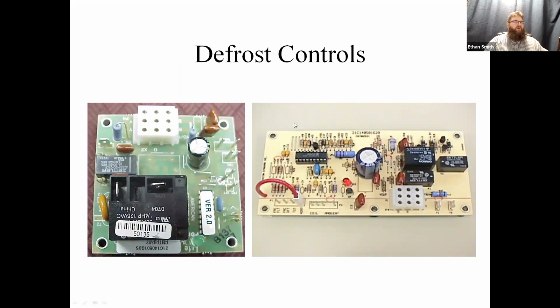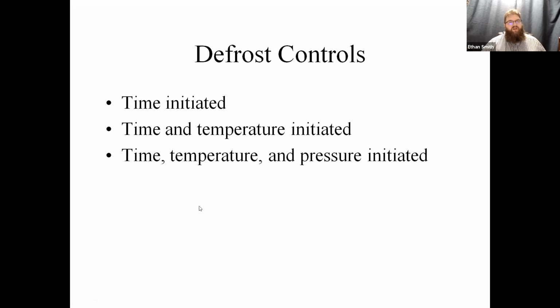Okay, let's talk about defrost controls here, guys. So there's several different types of defrost controls out there. The old ones were just time initiated. You'll still see these on refrigeration systems for like walk-in boxes, things like that, where it's just simply a timer. It defrosts for X number of minutes every hour or every 2 hours. Okay. We also have time and temperature initiated, where it'll actually take a temperature of your evaporator and determine whether it needs to defrost or whether it can wait another cycle. We also have time, temperature, and pressure initiated.